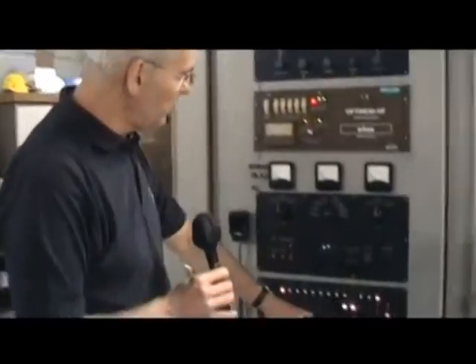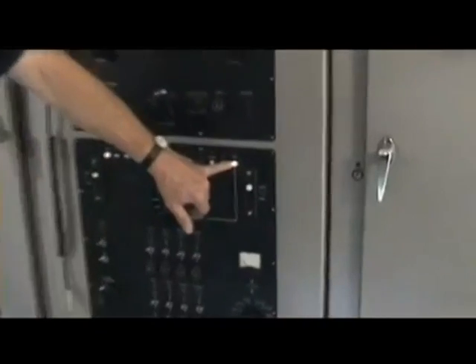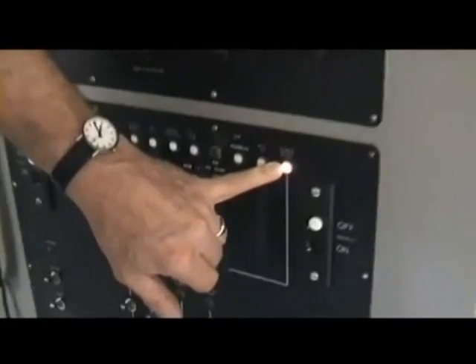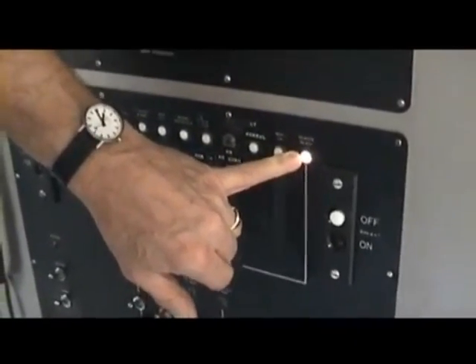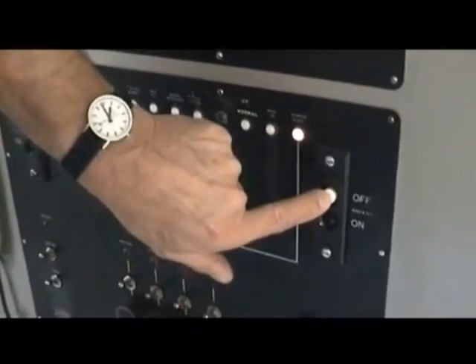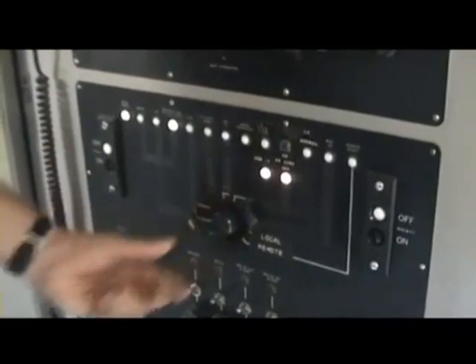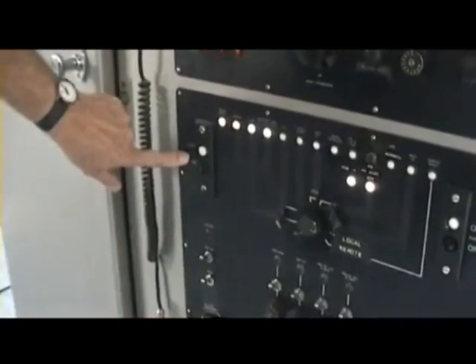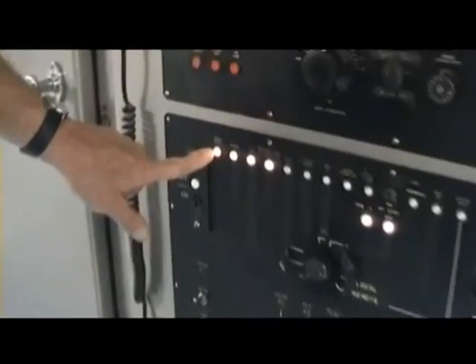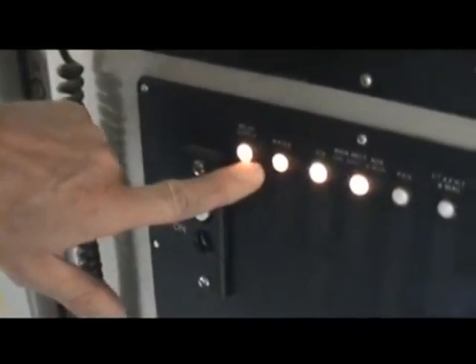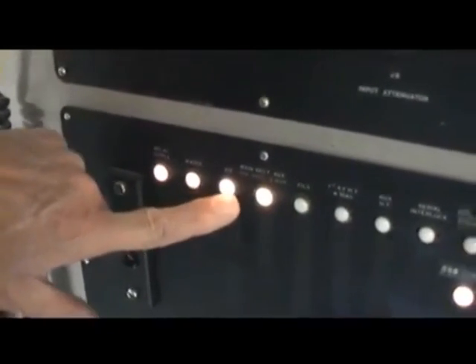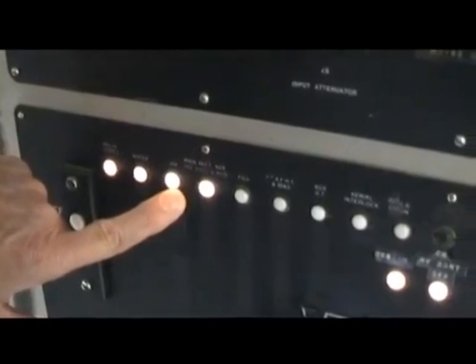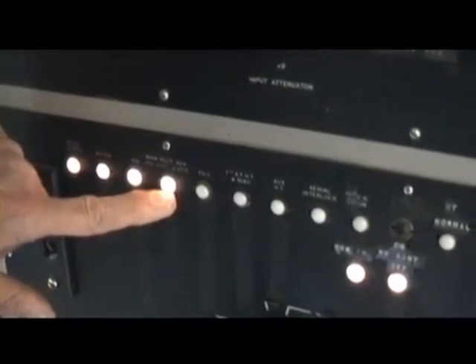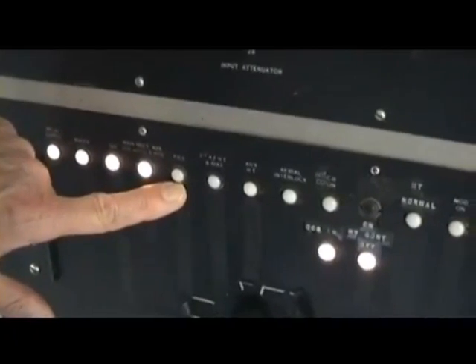So that's that. It's in remote control at the moment. The light says so, so it must be. I'm going to take it off remote and power it up manually. So let's take the HT off. Let's put it to local. This one's already on. So up we go. We've got relay supply, we've got the water coming up, it is already there, the air supply's on. Preamp's got its supplies, and we're just waiting now for the filaments to light.